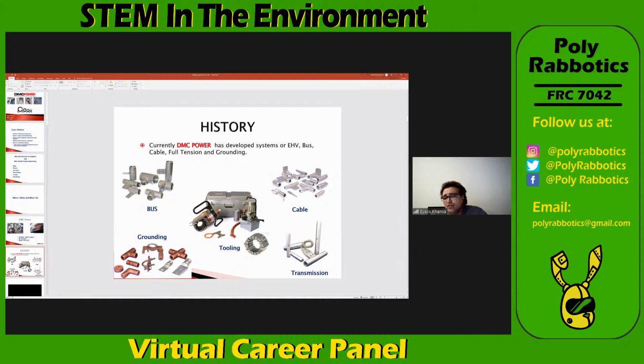How do we do that? We put the cable inside the barrel and squeeze it, using an electrical pump. That pump has oil in it and pushes it to 10,000 psi pressure, which converts into axial load in the tool to squeeze the tube onto the cable or conductor. That force can vary in our tools between 45 tons and 125 tons.